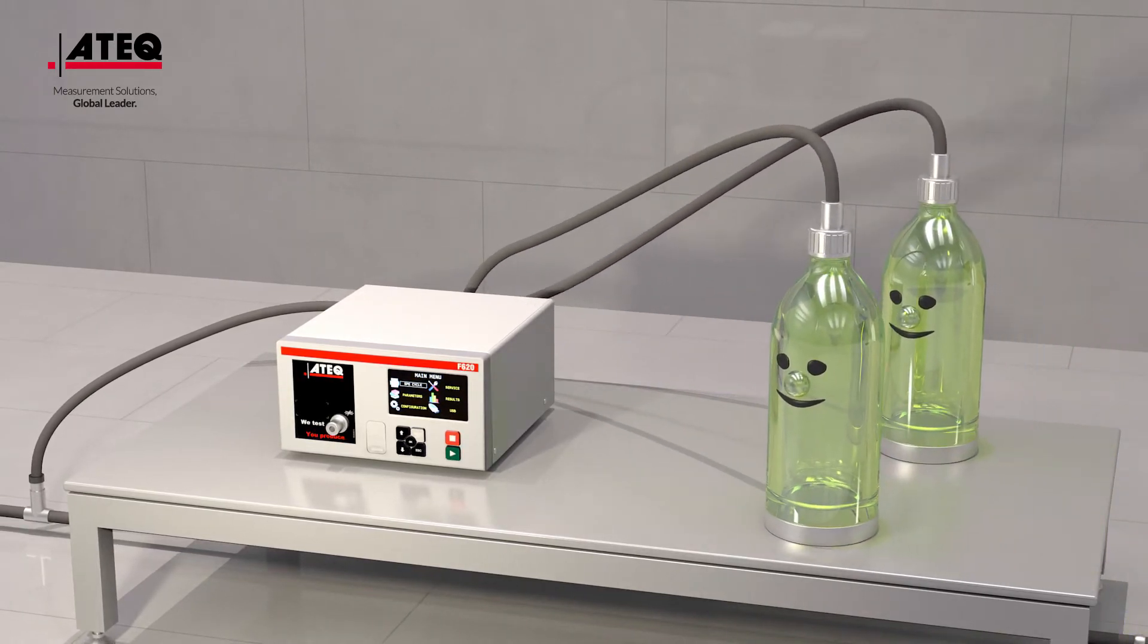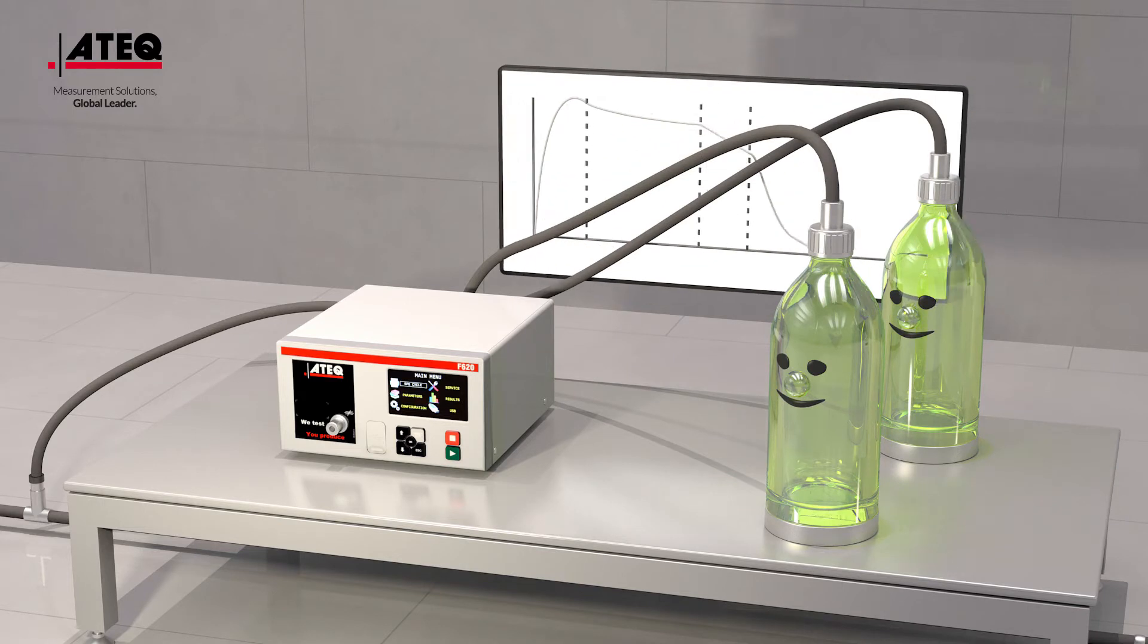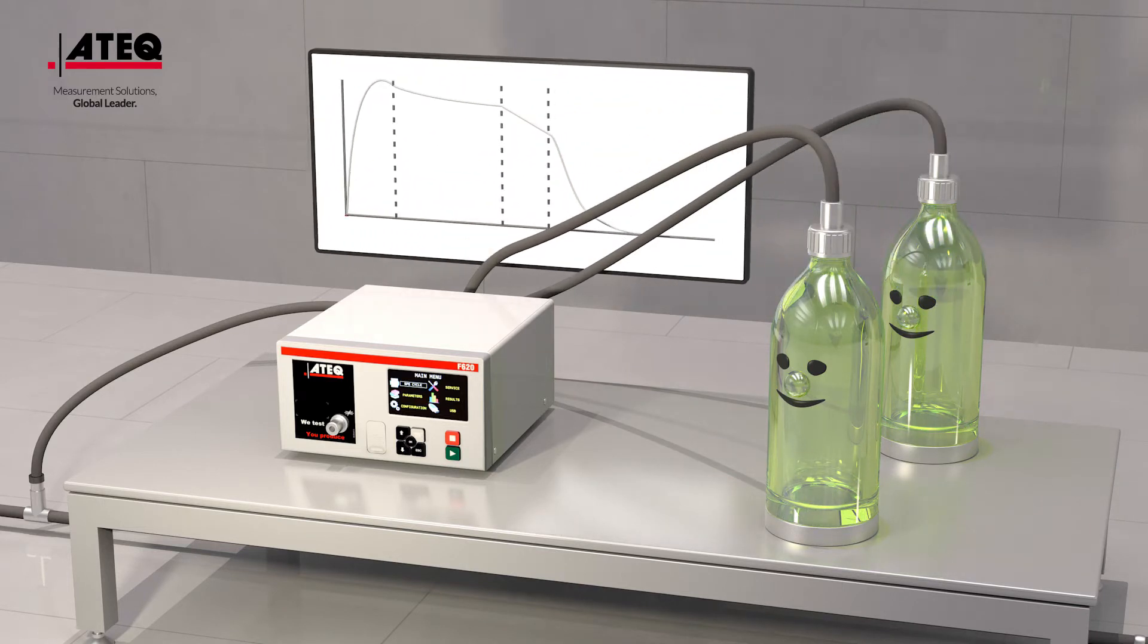The principle is simple. A part with a potential leak and a sealed reference piece are filled with pressurized air. The filling time is followed by a stabilization time used to eliminate the micropressure variations that disturb the measurement.